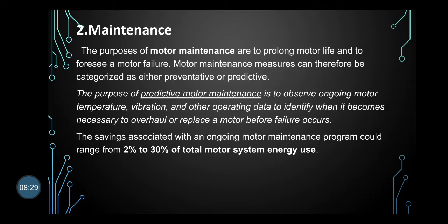In case of predictive maintenance, we observe the motor while it is operating, that is, we observe changes in temperature, changes in vibration, and different operating conditions, note down those operating data, and replace the different parts as necessary. The savings associated with an ongoing motor maintenance program could range from 2% to 30% of the total motor energy use. Means 2 to 30% energy can be saved.